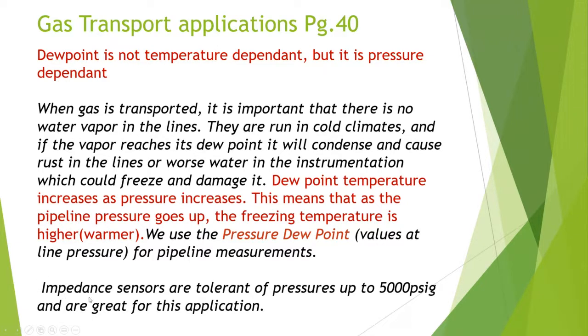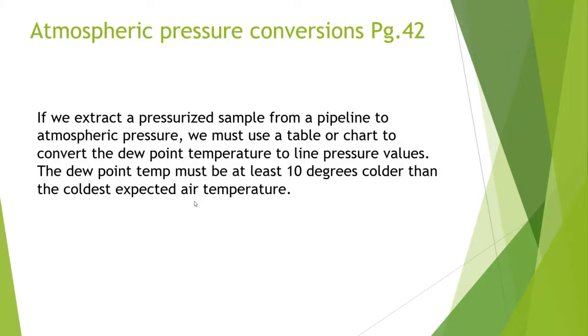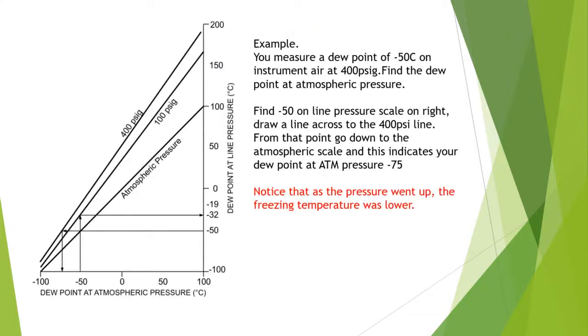Impedance sensors — good for up to 5,000 PSI — are among the more common devices used for pipeline dew point measurements. When working at atmospheric pressure rather than pipeline pressure, conversion between pressures is needed. If a sample is extracted from a pressurized pipeline to atmospheric pressure, density and other properties change. A table or chart is required to convert dew point temperature to line pressure values. Remember: dew point temperature must be at least 10°C colder than the coldest expected ambient temperature.